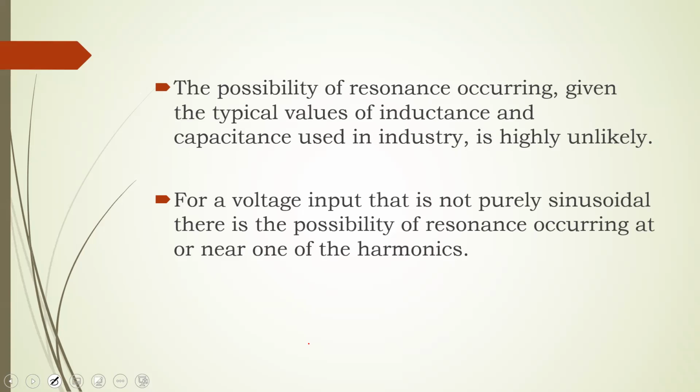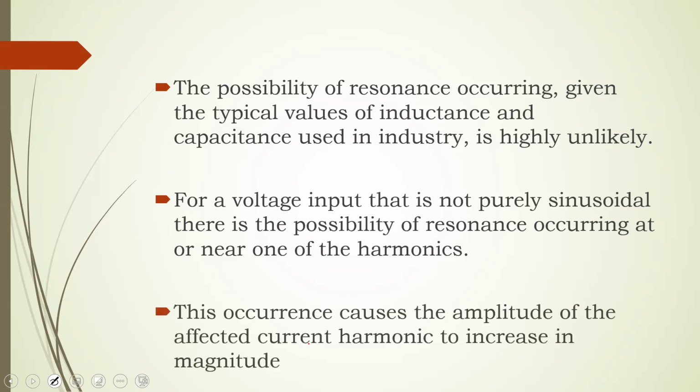Now, I'm not using 150 hertz in my system, but the fact that I now have a square wave being produced, that square wave, as we have just shown, will have a fundamental at our power frequency, which is 50. But it also has a third harmonic, which is 150. And it has a fifth harmonic, which is 250, etc., etc., etc. So because you now have these additional frequencies, the possibility of resonance increases. That's all we are saying here. Now, what do we know about resonance? We know that at resonance, you have the maximum amplitude for your current, series resonance, that is, yes?